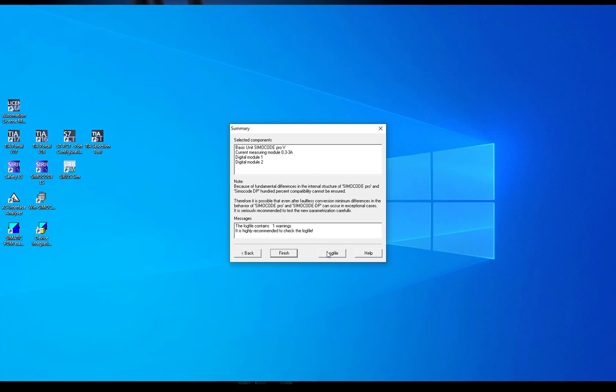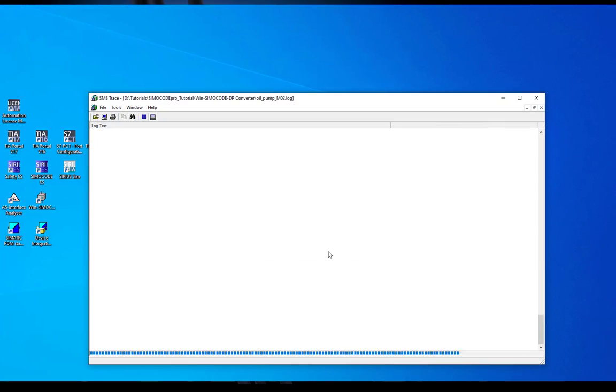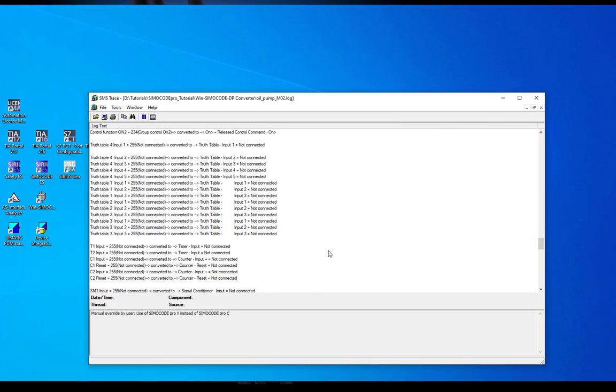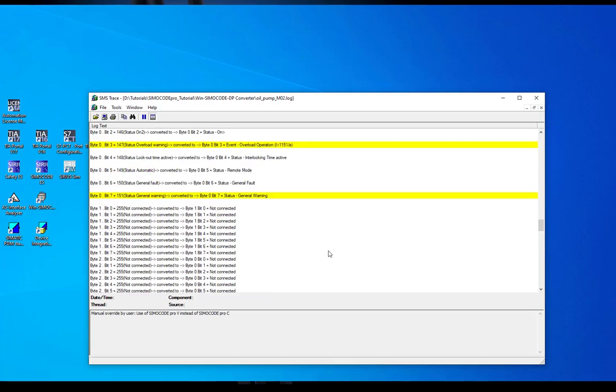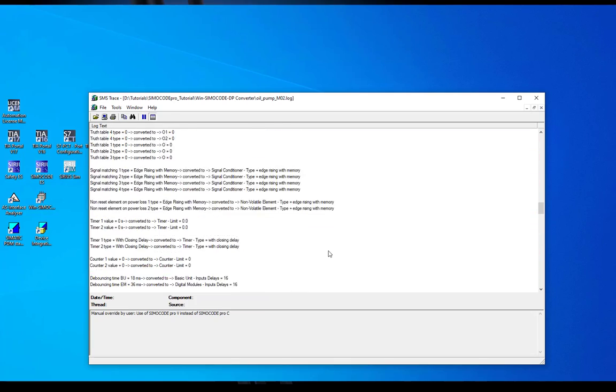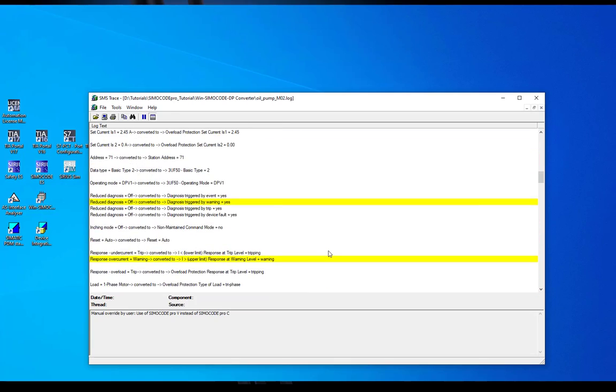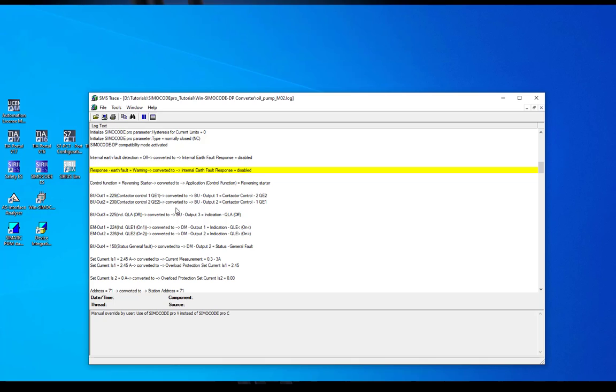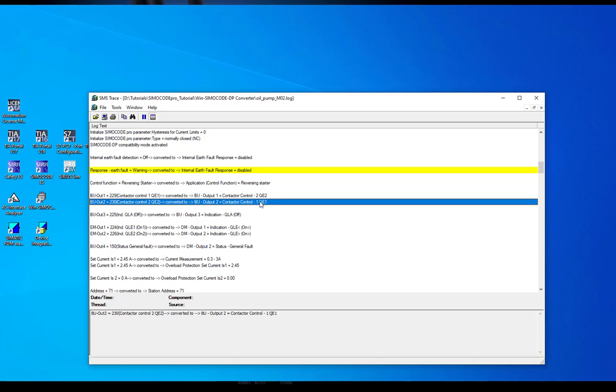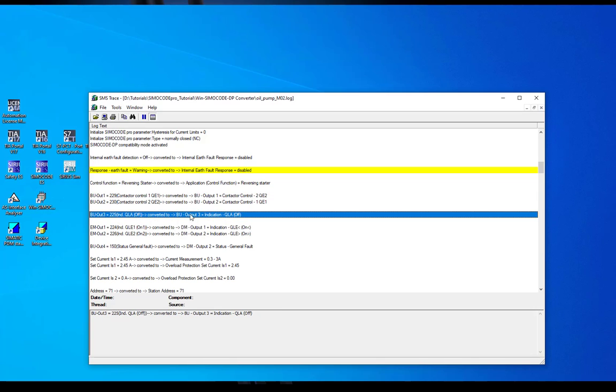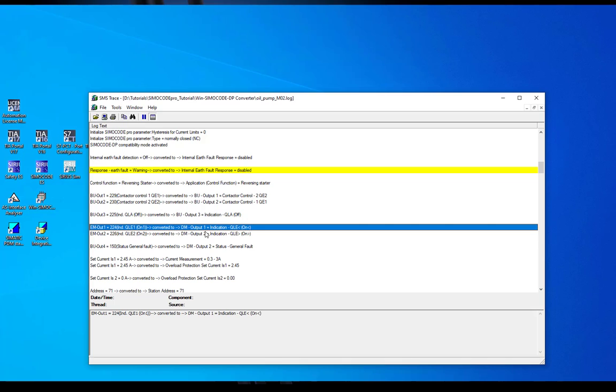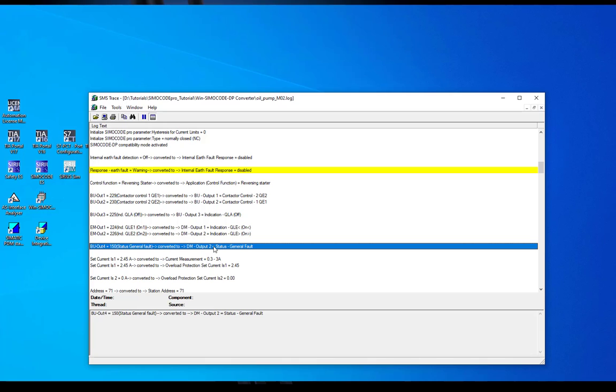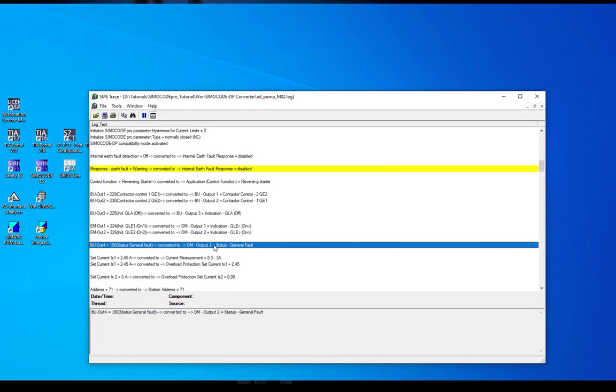So let's have a look into the log file. Here you can find every step performed by the converter. Here for example the assignment of the output relays of basic unit outputs 1, 2 and 3. This was converted to the SimoCode Pro basic unit. The expansion module outputs were converted to one digital module and the basic unit output 4 was converted to another output of a second digital module.